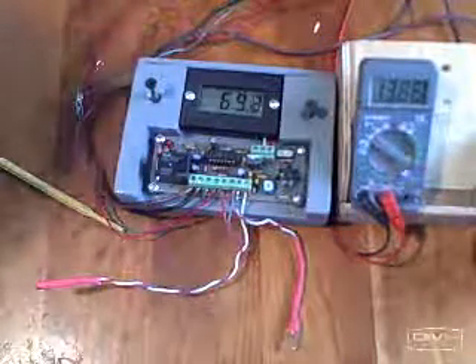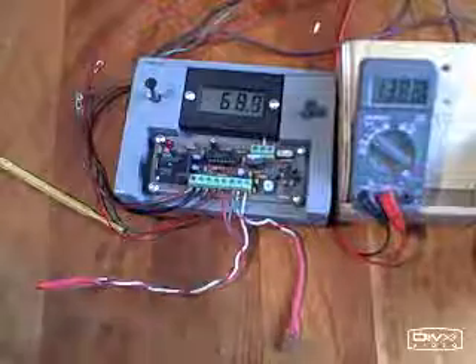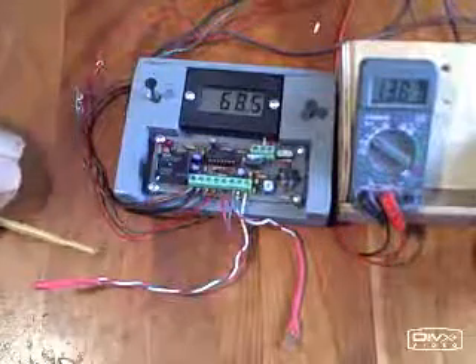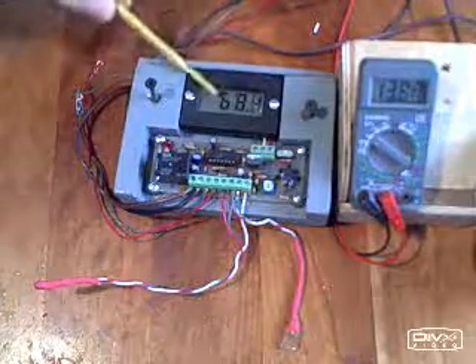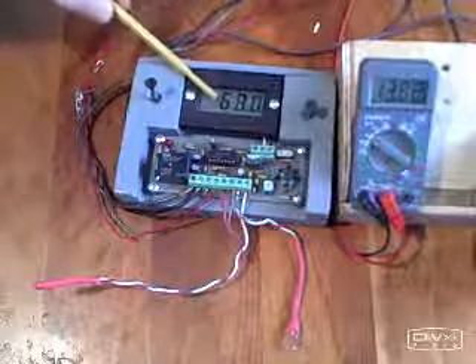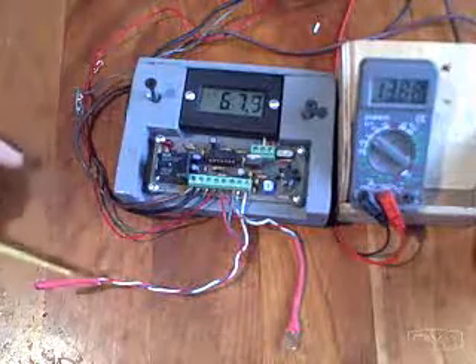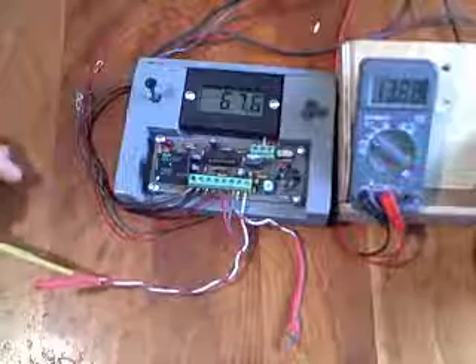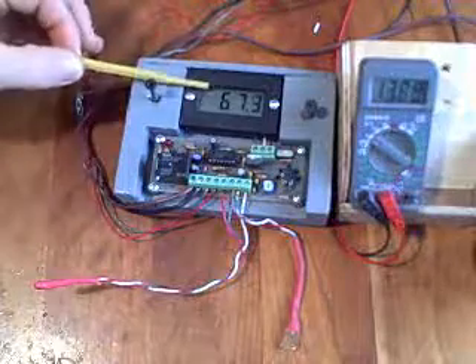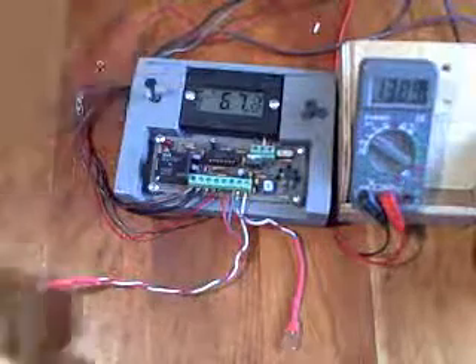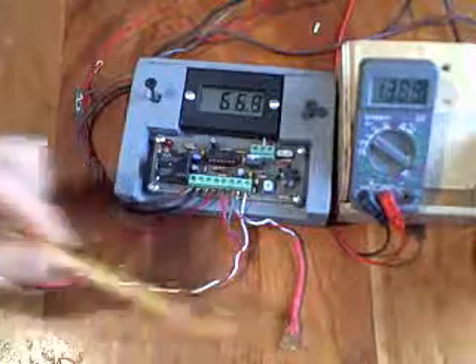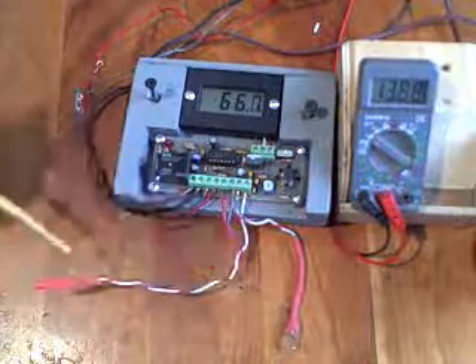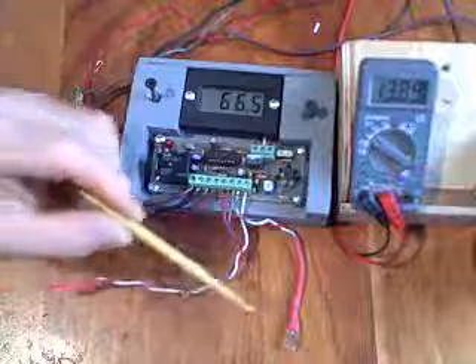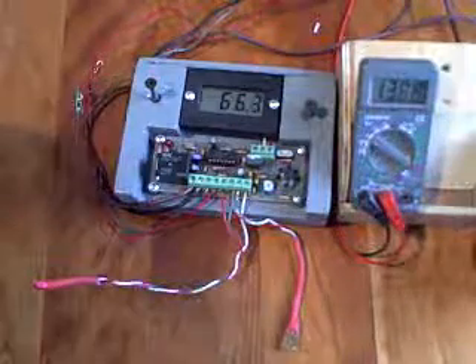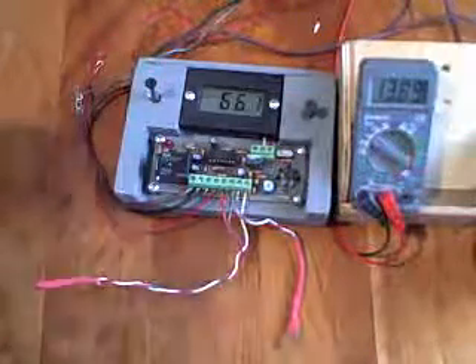Okay, what we're looking at here is a differential thermostat. You can see the actual temperature. This is the temperature in the collector right now. Well, actually, it's the probe that would go to the collector that is monitoring that temperature. But basically, this would be the collector temperature, and this would be the tank temperature. So when the difference between these temperatures is substantial, this should turn the pump on.